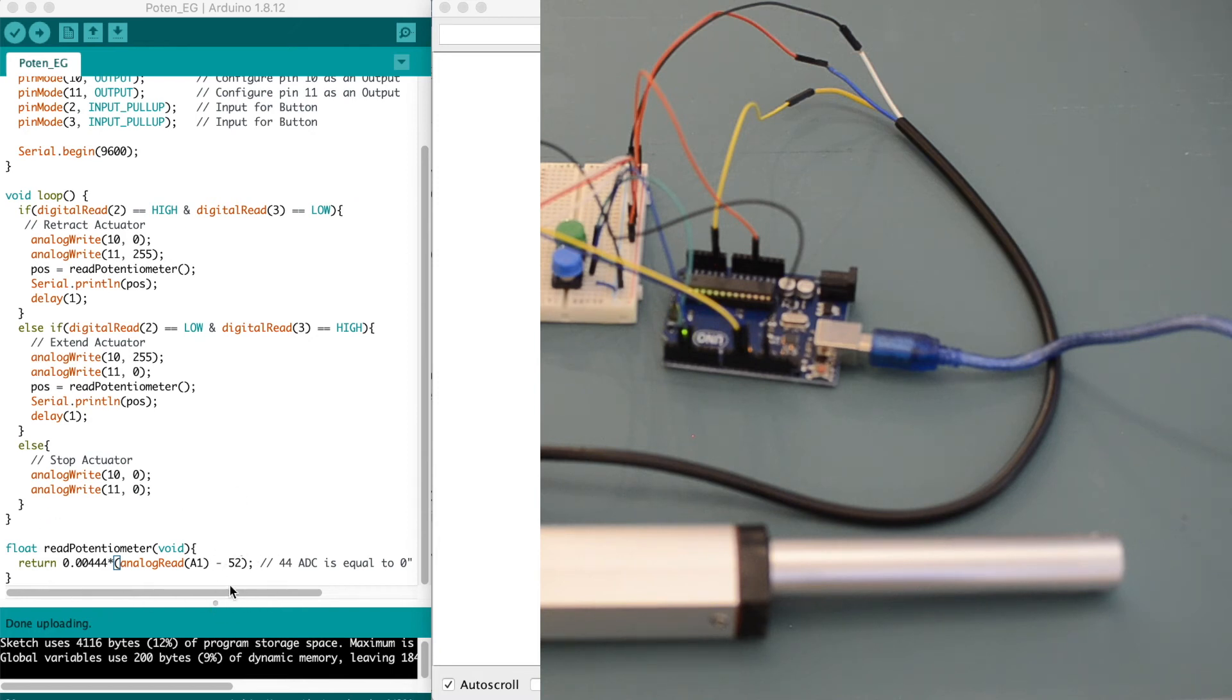You can see the 52 to balance it out to zero, and I have this value by just using the range, which was 952 to 52, and my stroke length, which was 4 inches to 0 inches, and came up with this value here.